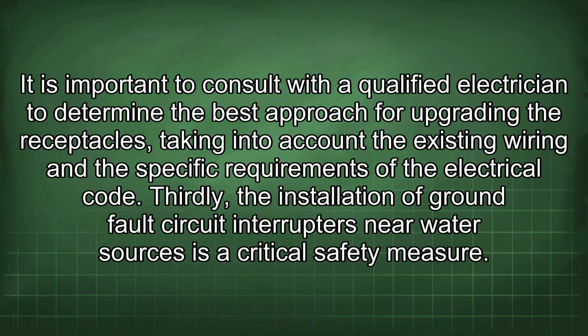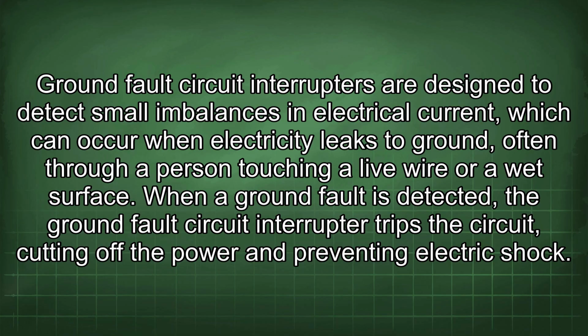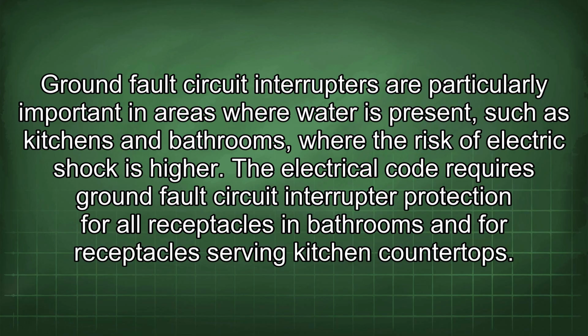Thirdly, the installation of ground fault circuit interrupters near water sources is a critical safety measure. Ground fault circuit interrupters are designed to detect small imbalances in electrical current, which can occur when electricity leaks to ground, often through a person touching a live wire or a wet surface. When a ground fault is detected, the ground fault circuit interrupter trips the circuit, cutting off the power and preventing electric shock. They are particularly important in areas where water is present, such as kitchens and bathrooms, where the risk of electric shock is higher.